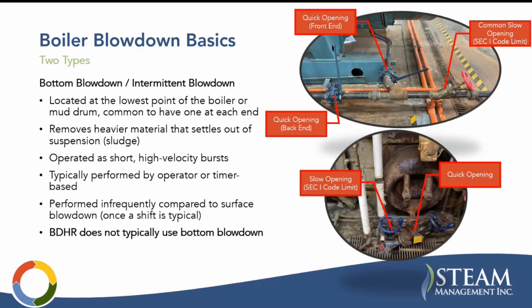These are performed infrequently compared to surface blowdown. So like once a shift is typical. So this represents a lot smaller energy waste than surface blowdown. And it is literally a few minutes every 8 hours. So it is not a good candidate for a heat source for a heat recovery opportunity.